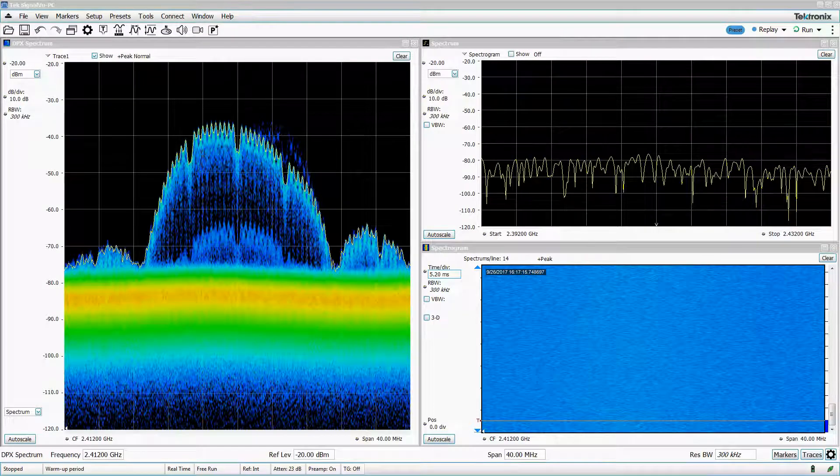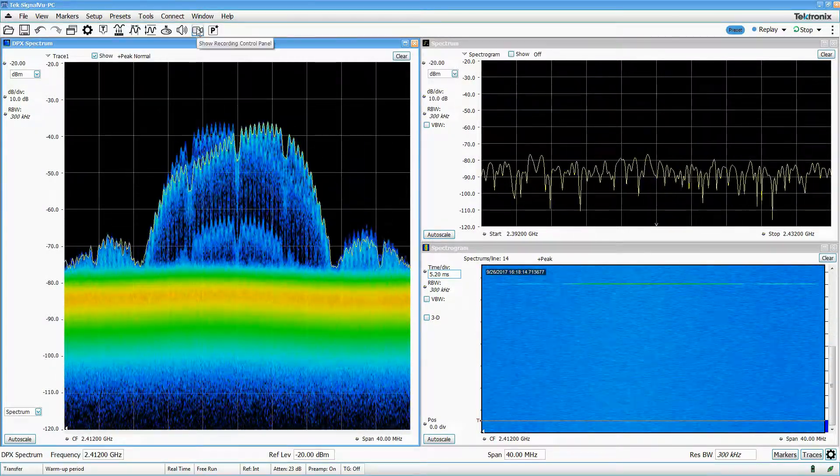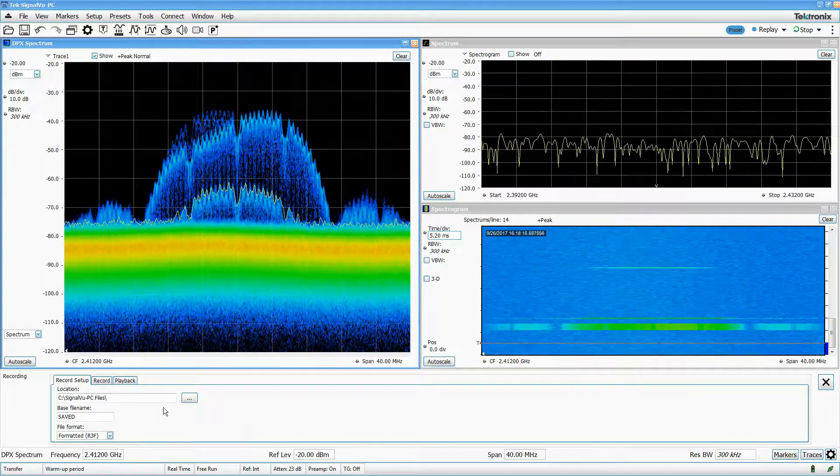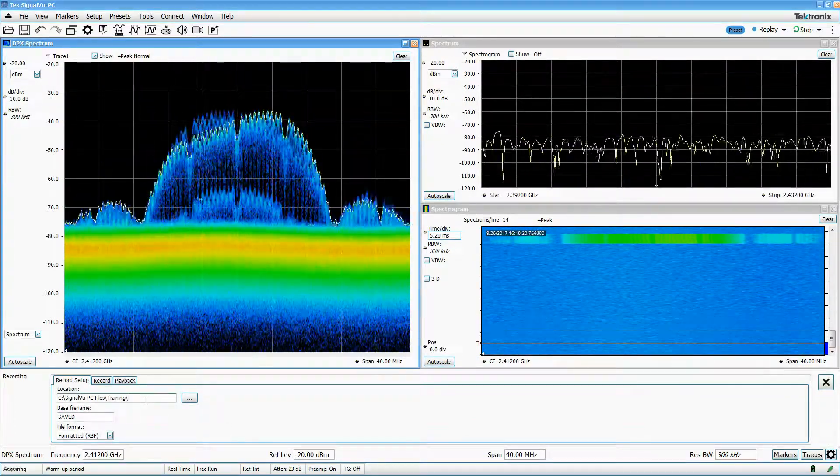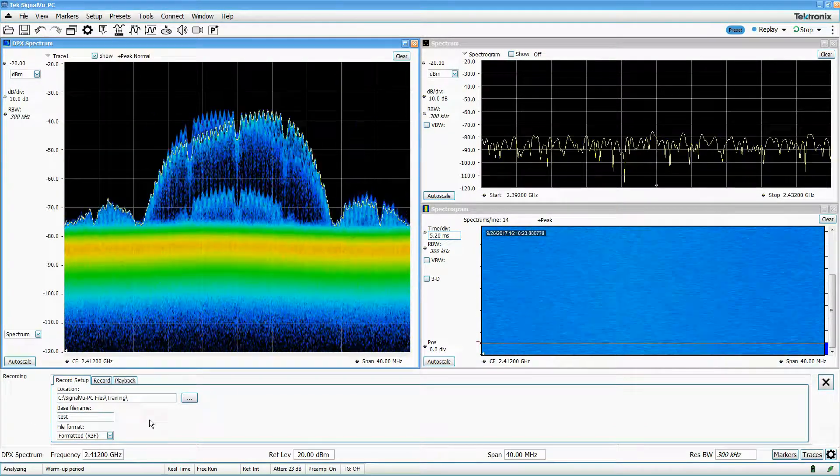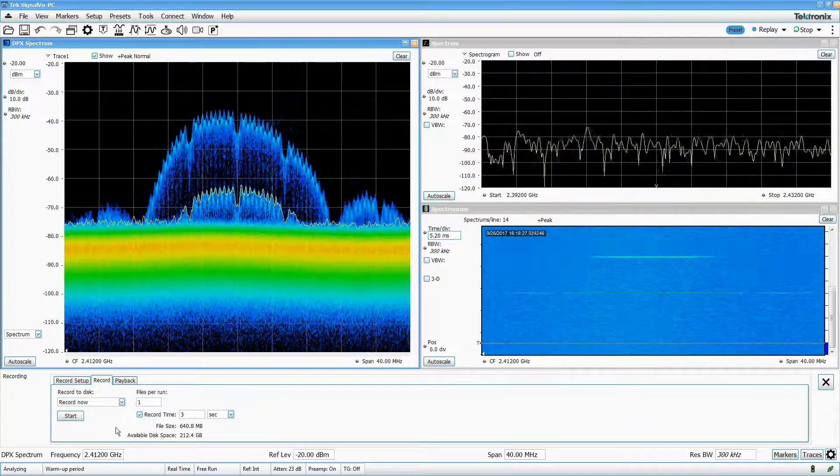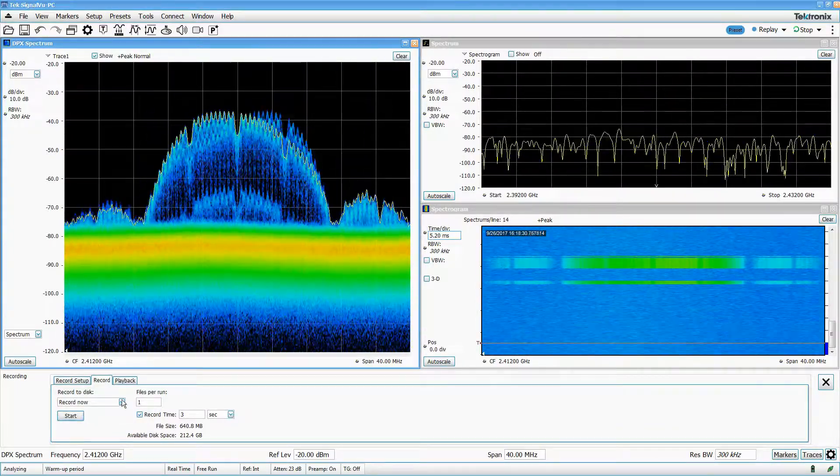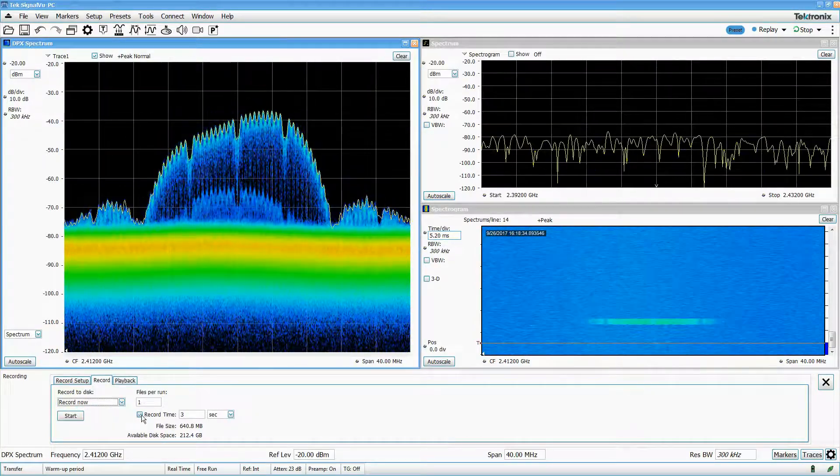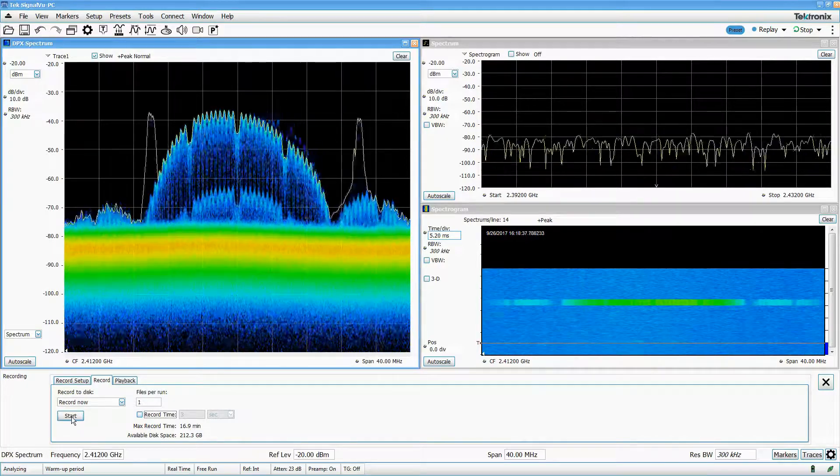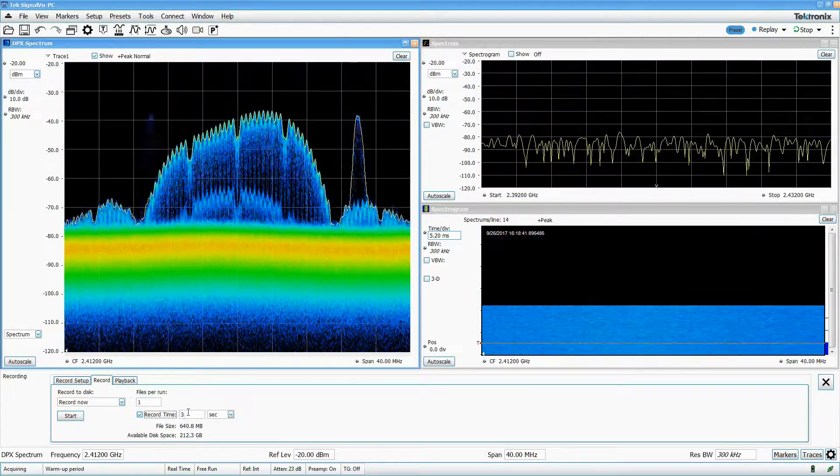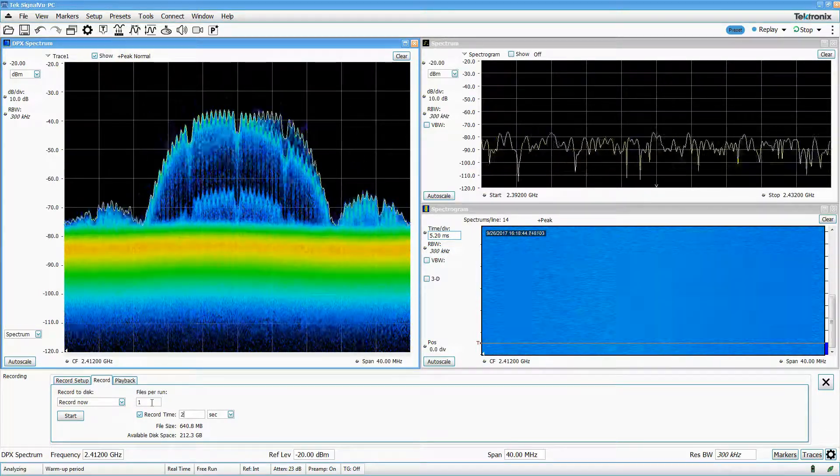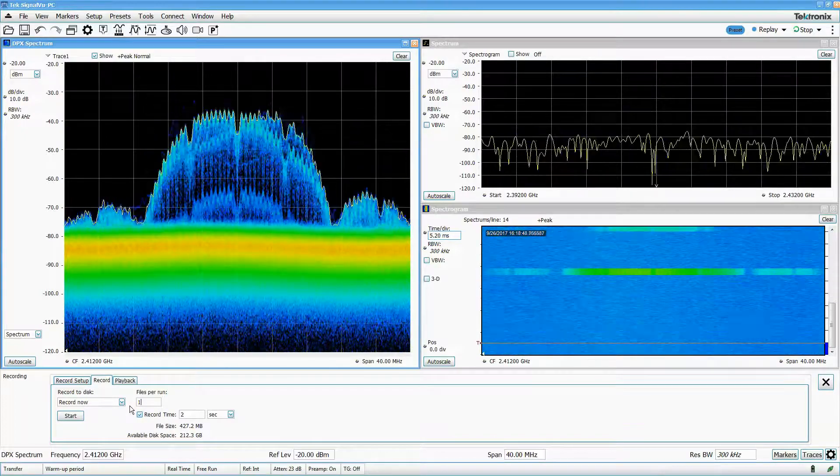To save contiguous streaming data as a .r3f file, I click on the recording icon. I'll choose my location and set my base file name, and then switch to the record tab. I can configure my recording to begin when I click a button, or I can have it begin when a trigger occurs. I can also configure my recording to end when I click the button, or I can set a timer that will automatically stop the recording when it reaches a certain length. I can also set the number of files per run if I want to make multiple recordings back to back.